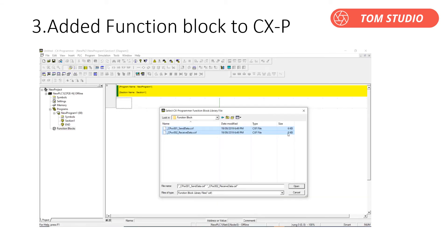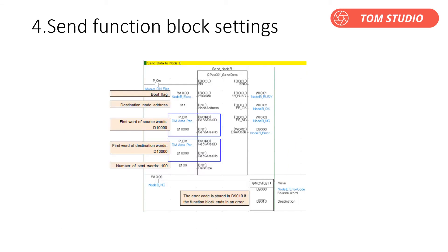Adding the function block is pretty easy — you can either copy and paste from the example program, or import the function block from an individual file. Laying out the function block is very straightforward: copy and paste it into your program or import it, then fill in all the parameters — such as the trigger bit, node address, first word of destination words, and number of sent words. Omron has made networking much easier than before: there is no need to use CX Integrator to set up the network number. This function only requires setting up the FINS network address — no need to set up the network number.